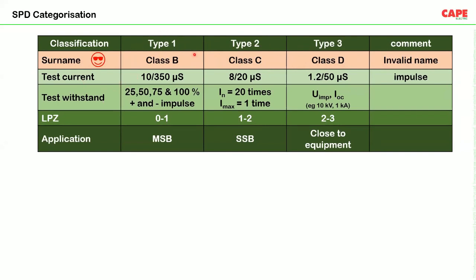Type 1 is an SPD which is tested with an impulse current of 10 by 350 microseconds. Type 2 is an SPD tested with 8 by 20 microseconds. Type 3 is tested with a voltage impulse of 1.2 by 50 microseconds. The first two are current impulses, and the third one is a voltage impulse. We have explained 10 by 350 and 8 by 20 in the previous seminar. I don't want to explain it again.